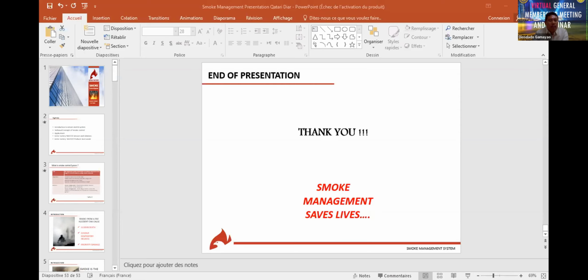Alright, if the car park is actually using the CO system, it will help the client reduce the consumption of energy. So that's why you have stages: less than 30 ppm, between 30 and 50, more than 50. Some car parks have no CO system, so they have to run at 6 air change all the time, and then it will change to 10 air change after there is a fire. So that's why you can find some car parks with 6 air change where the fans are running 24 hours, because they don't have a CO system. If they install a CO system, it will automatically follow the stages. Yeah, I think that is the old design. The new design right now is about the jet fans. It runs according to the level of pollution. Anyhow, thank you.